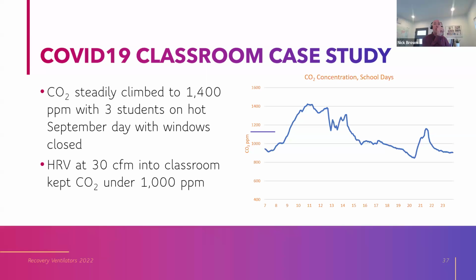Here's another case study from my house. During COVID, my daughter invited 2 friends over to do high school in this very office. And I had my air quality monitors in there, and this is what it saw. At 7 a.m., under 1,000. By 9 a.m., it was going up above 1,000. By lunchtime, it was above 1,400. And so I was worried, hey, they're going to get sleepy. They're not going to perform that well. COVID stuff enough. Let's see what an HRV does. And that's what prompted me to install the main house HRV. I put 30 CFM into that classroom, and that kept the CO2 level under 1,000 parts per million, which was a victory. That was the precise goal. And I have that now benefiting my home office.